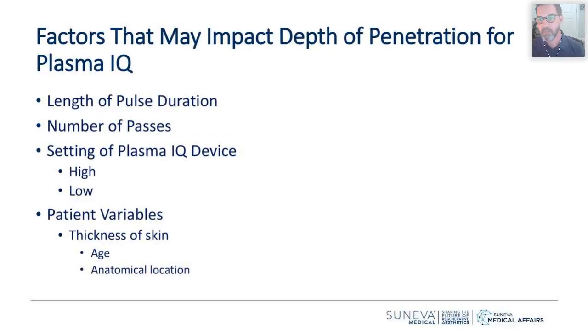So factors that are going to impact the depth of penetration, we've already talked about length of pulse duration. Number of passes, really 1 pass is going to be sufficient. You're not going to need to do multiple passes to get better results. Delivering the energy for longer periods of time may seem like a good idea to get a better result, and that is not necessarily the case, again, because of the risk that you run around scarring and potential hyper or hypopigmentation. We'll show you what the device looks like in just a moment. It does have a high and a low power, but we're pretty focused on making sure that you remain on that low power as you're getting comfortable with use of the device. And of course, thickness of the skin and patient's age. If you have somebody that's very, very old, very paper thin skin, you're obviously going to want to use a lower power on perhaps very quick passes or very quick delivery of energy as compared to somebody with very thick, glabrous skin. And so you're going to be able to modify it a little bit as it relates to that particular issue.